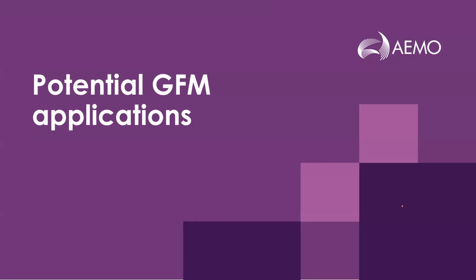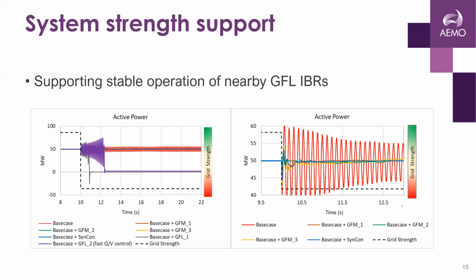The next few slides are on potential grid-forming applications, based on desktop analysis. The first is system strength support, which I partially discussed yesterday. On the left-hand side—let's focus on the right-hand side figure, which is easier to visualize—when you have a baseline with a grid-following inverter, a step change in grid strength would excite oscillation. If you have a grid-forming inverter sitting very close to that grid-following inverter, you can see it stabilizing the oscillation, and you don't see any oscillation.